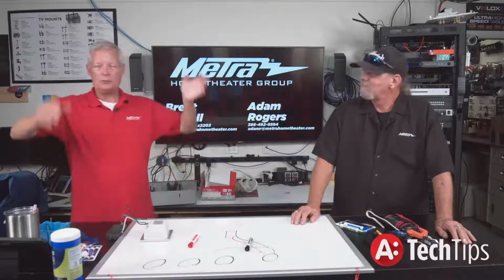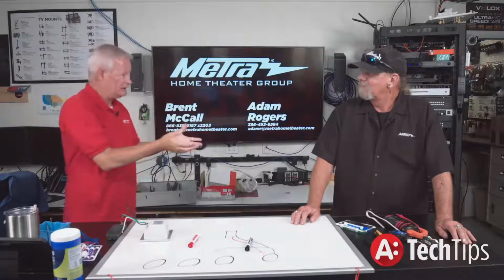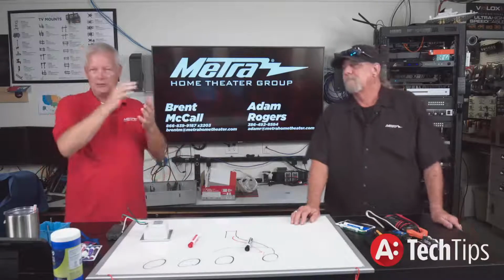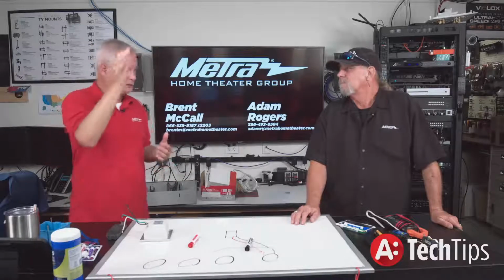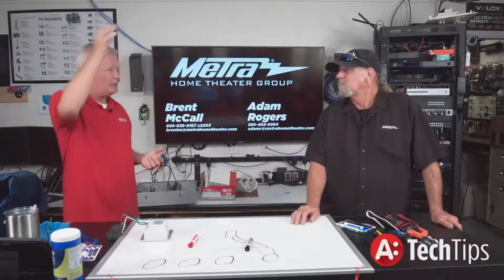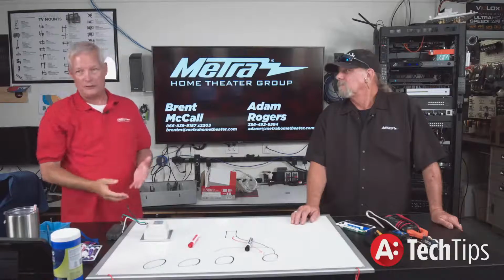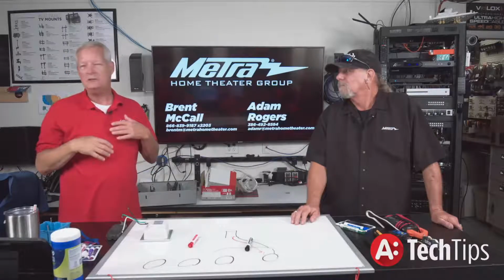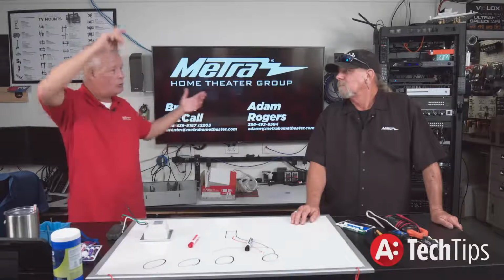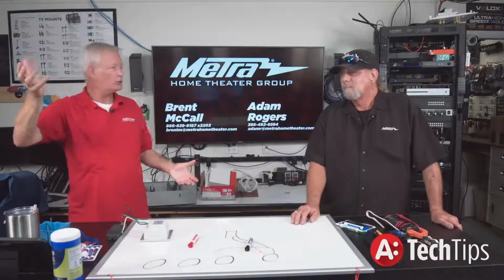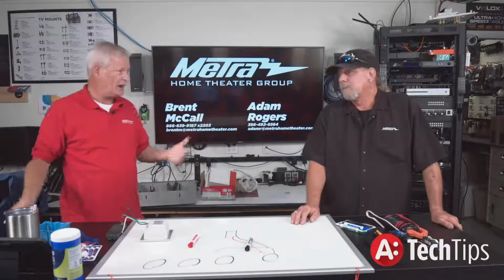What we would do is put a can above the automated lighting can. That's what we did. And then if you had a constant, you could break that off right off the circuit breaker, and then the switched into the automated panel. If you wound up not needing the switch load, you would just ignore it at both ends and treat it like a regular outlet, or two switch loads.